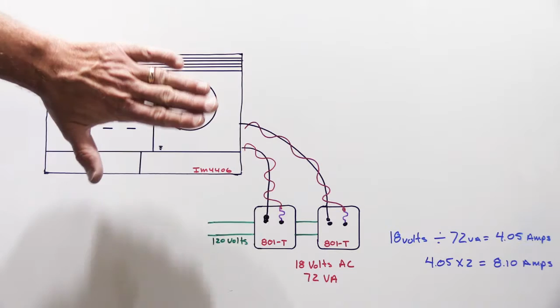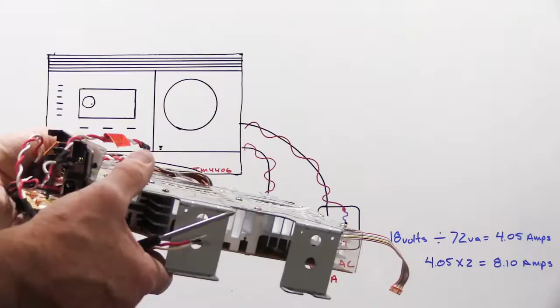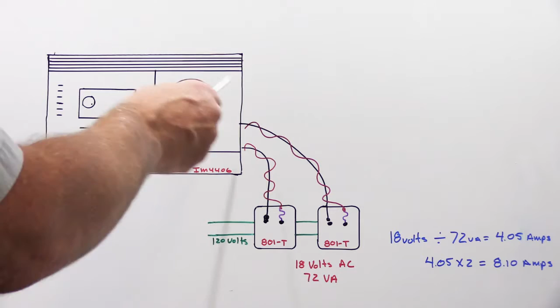Now, this is fine as long as your IM or IMA4406 works properly, but as systems age, problems can occur — sometimes you'll have a failure in the master station, specifically in the power module, in this section which I have a fairly extensive write-up about with pictures on our website. If you have a dramatic failure in the power module, it can overload one or both of the 801Ts, and because they have fuses built in, it blows the fuse. In this case, we're going to say it blows both fuses.